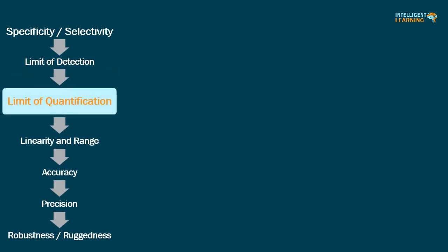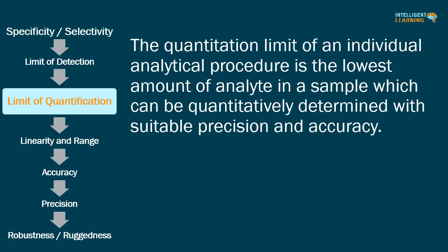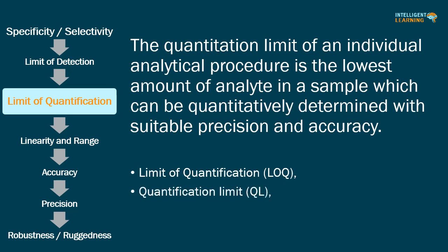The limit of quantification (LOQ) is defined as the lowest amount of analyte in a sample which can be quantitatively determined with suitable precision and accuracy. The quantitation limit is a parameter of quantitative assays for low levels of compounds in sample matrices, particularly used for determination of impurities and degradation products. Various documents use different terminology such as LOQ, quantification limit, or QL.